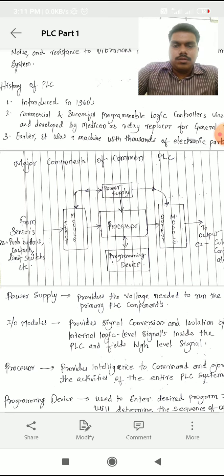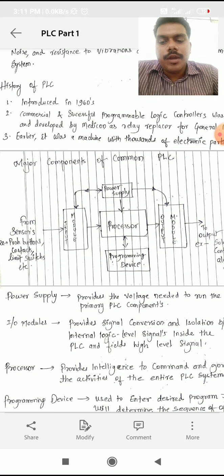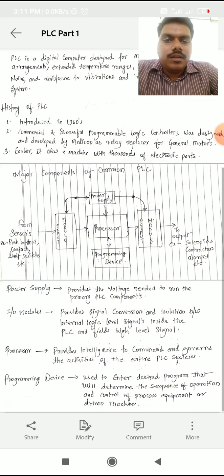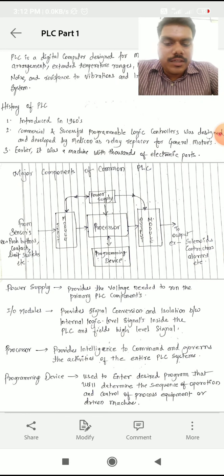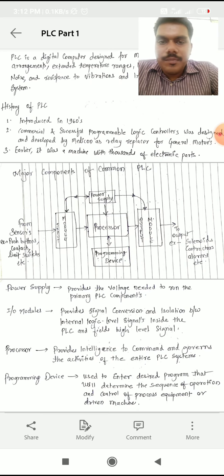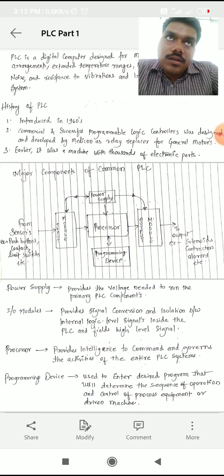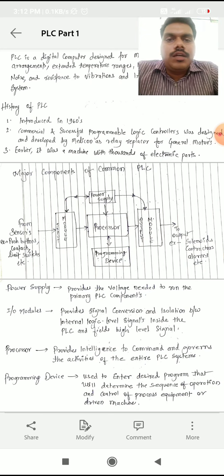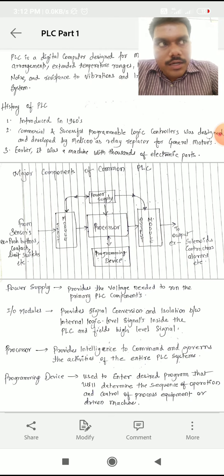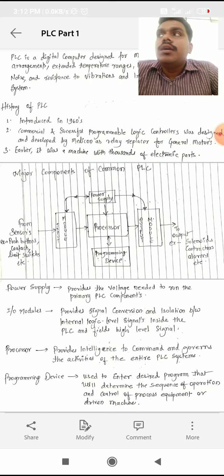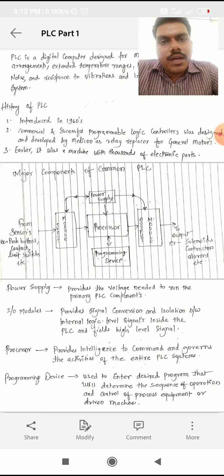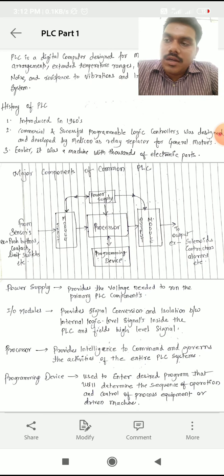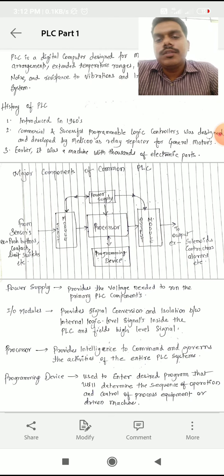Now let's see the basic parts. The power supply provides the power voltage needed to run the primary PLC components. The input module provides signal conversion and isolation between internal logic-level signals inside the PLC and field high-level signals. It provides signal conversion — if we are getting any signal in the form of voltage or current, it should be converted to an understandable logic so that the coming analog information from the sensor can be processed by the processor.